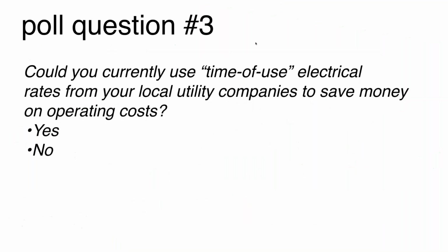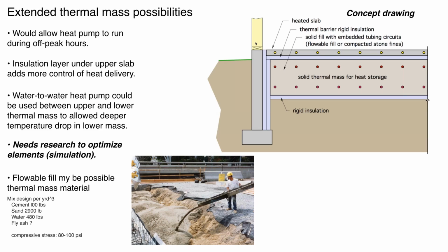Yeah, certainly it could be done. The slide that showed that extended thermal mass idea, certainly solar collectors could be used when there's solar energy available to inject heat into that solid thermal mass. The challenge with solar is you can't control when it's available. So you have it or you don't have it, and where do you park it when your building doesn't need heat but you have solar gains? So traditionally it's been done with thermal storage tanks, but for space heating, again, we get into the challenge of those tanks have to be very large, and as such, they're very expensive. So going back to a solid thermal mass with solar input, I don't see any reason why that can't be done.